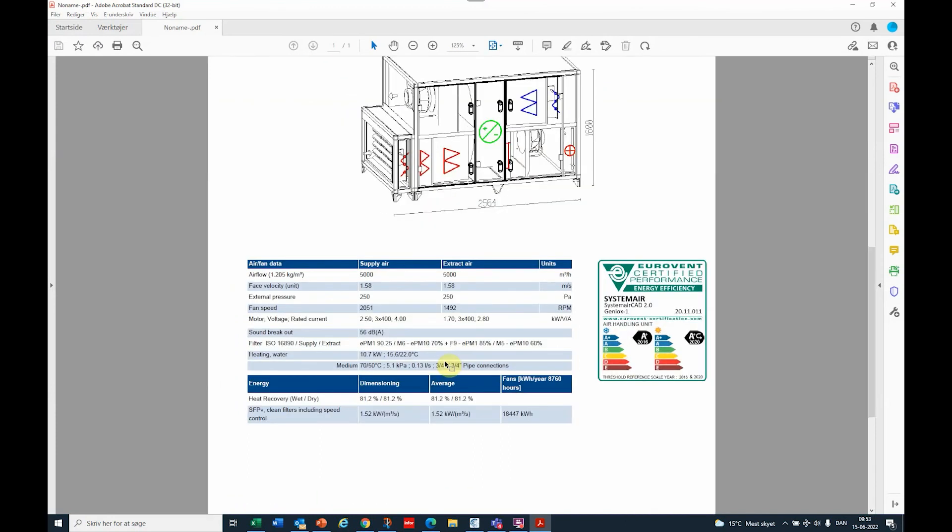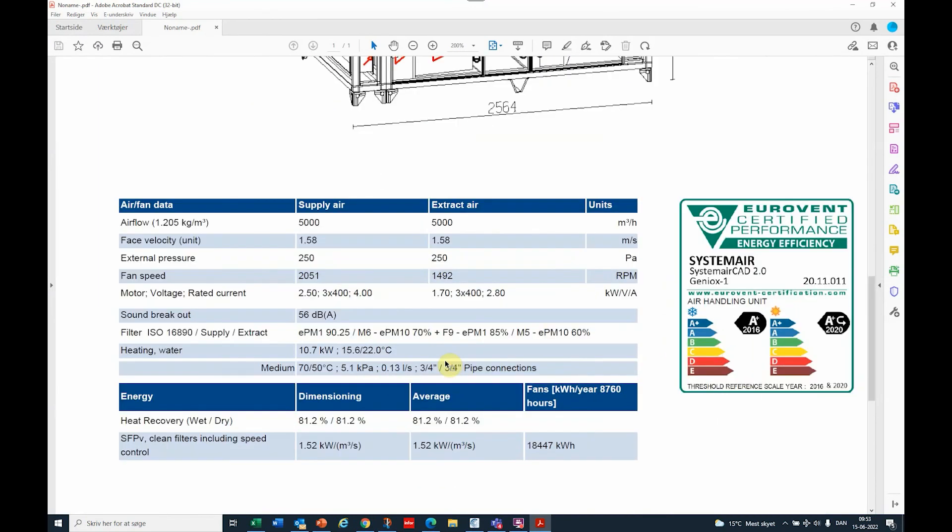If we look at the printout, then we introduce the value on the front page. If we zoom in a bit, then we can see that filter ISO 16890 is the first value on the filter: 90.25%. The supply air filter is EPM 10 70% plus an EPM 1 85% and the extract is an EPM 10 60%.